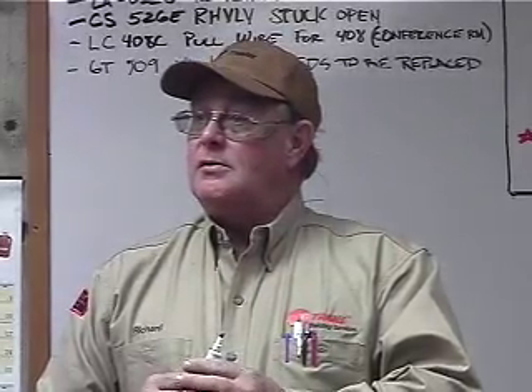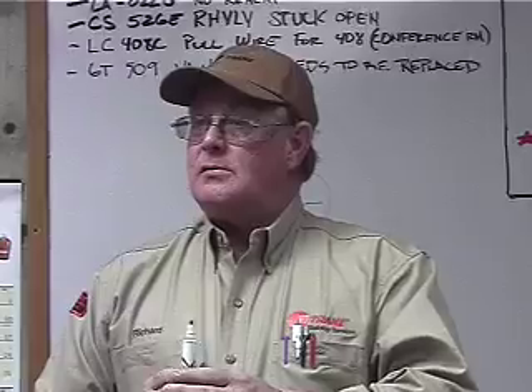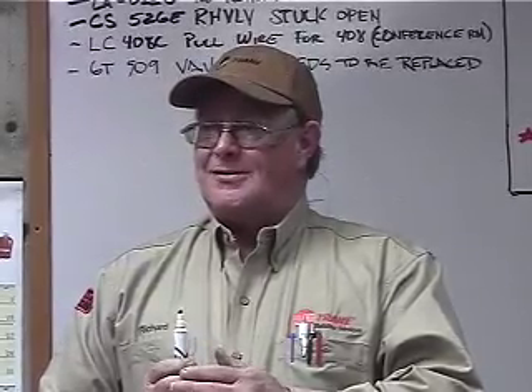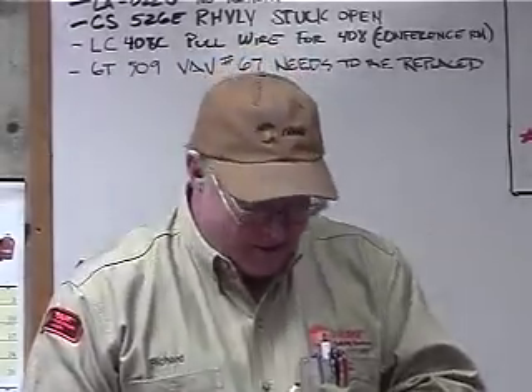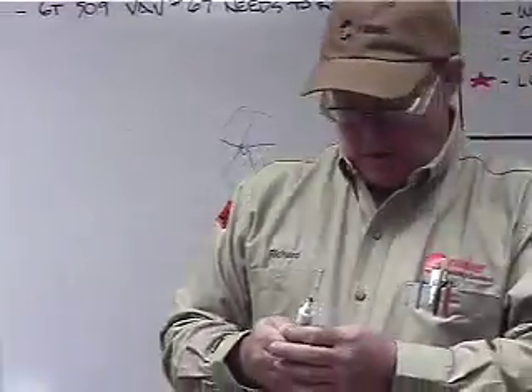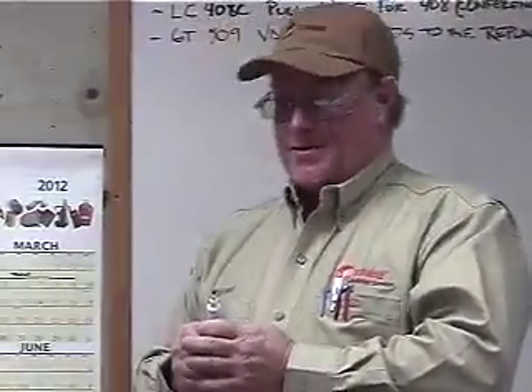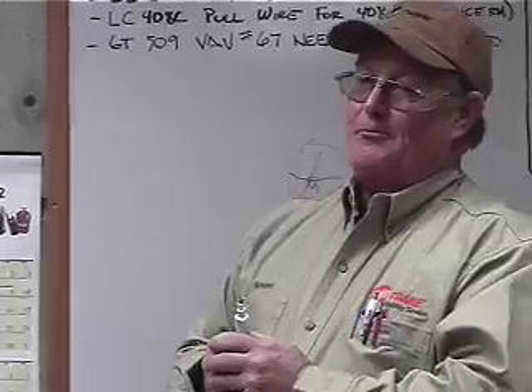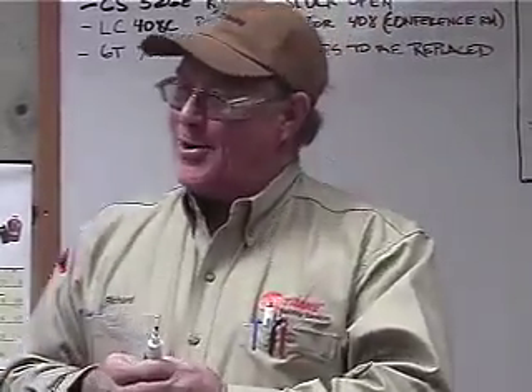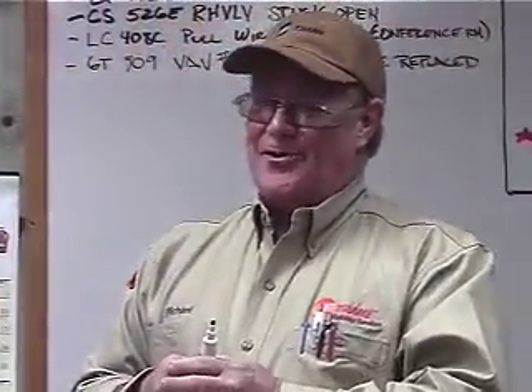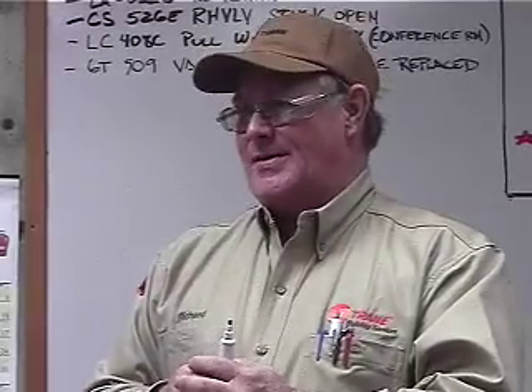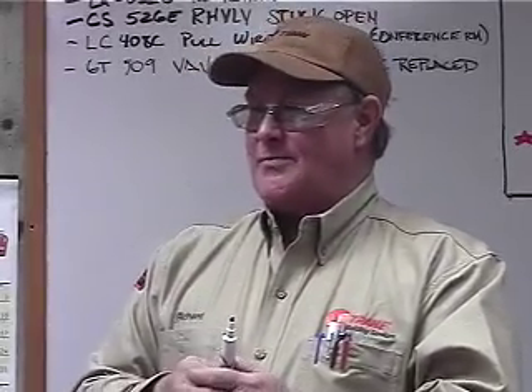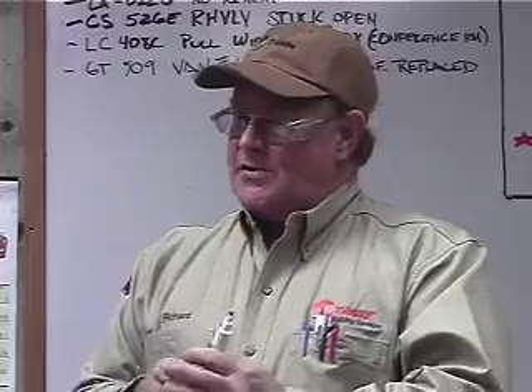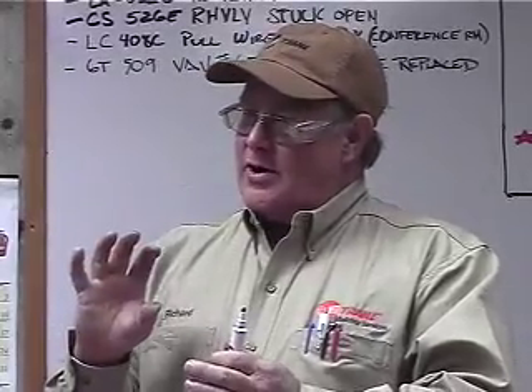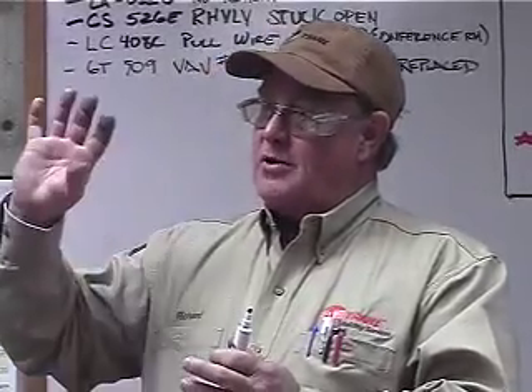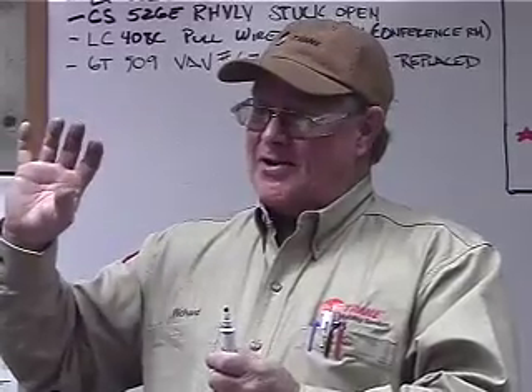So what happens when those vanes don't work? Say if they're stuck open and you don't have a load, or a very small load. What would happen is you'd have a heck of a problem. Your refrigerant temperature is going to drop. It's going to drop like a rock. But the only way that would happen is if you opened them up fully and they got locked into that position.